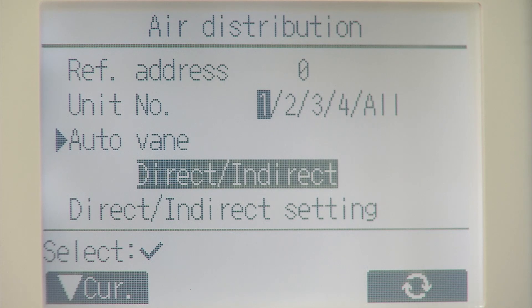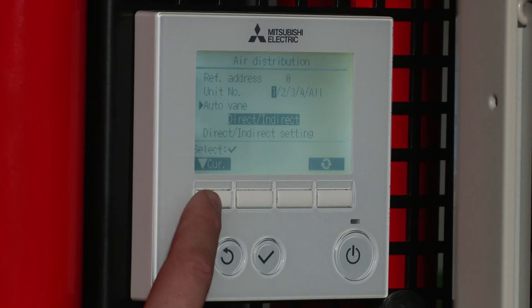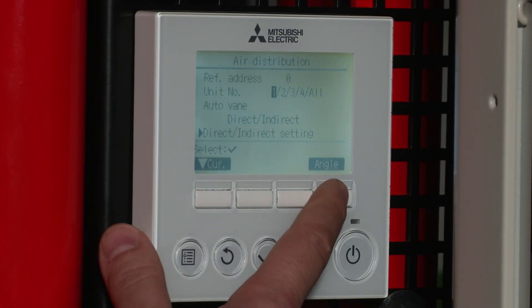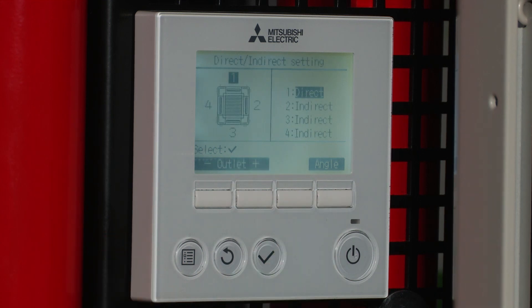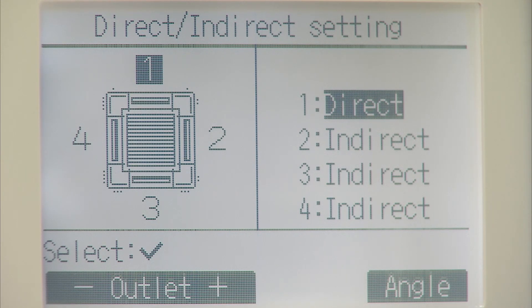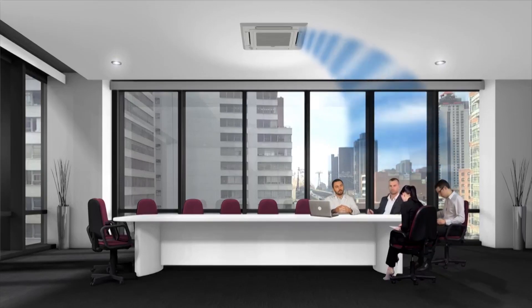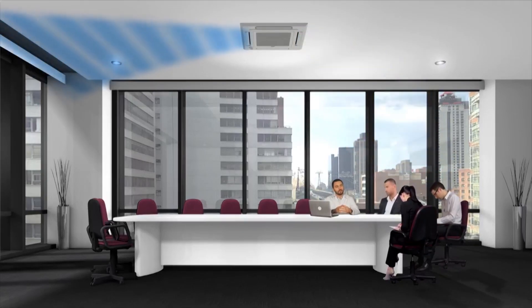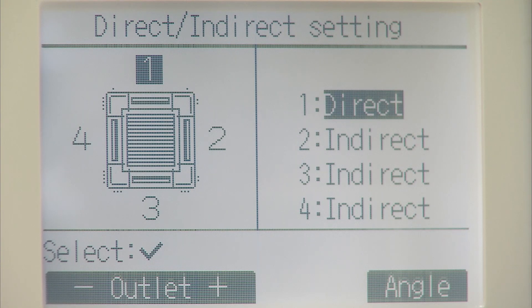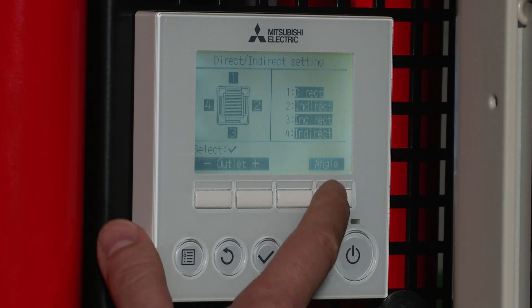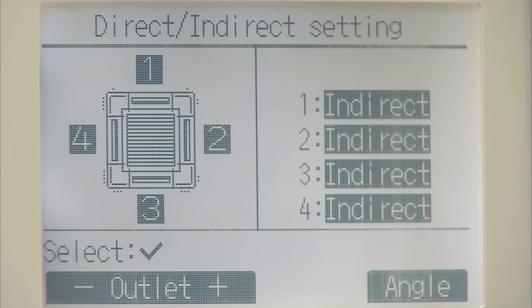On to the next option: direct or indirect. If I go for direct and indirect, I'm going to scroll down one more and set up that option. Then select on angle, and we've got the option of specifying whether we want to direct the air towards somebody or away from somebody. So it works out where people are in the room and can change the air flow depending on that. I'm going to select it so all the units are going to be set for indirect, so it's going to blow the air away from people.